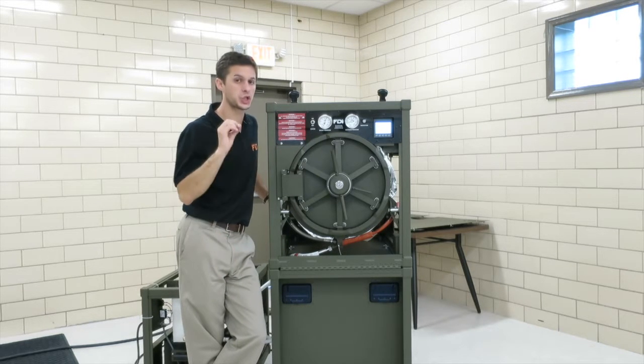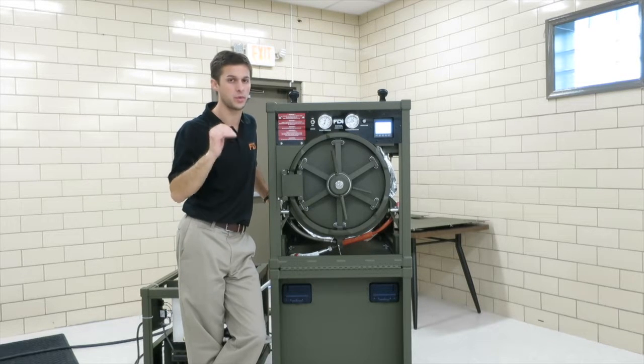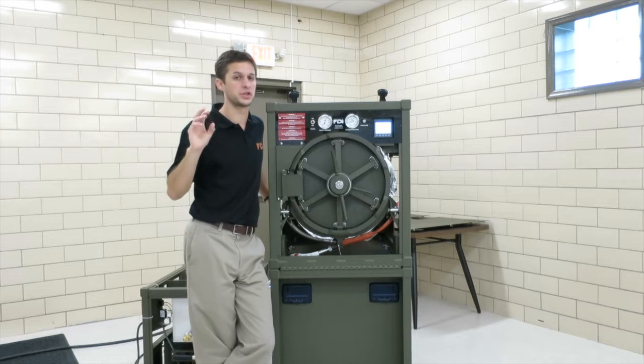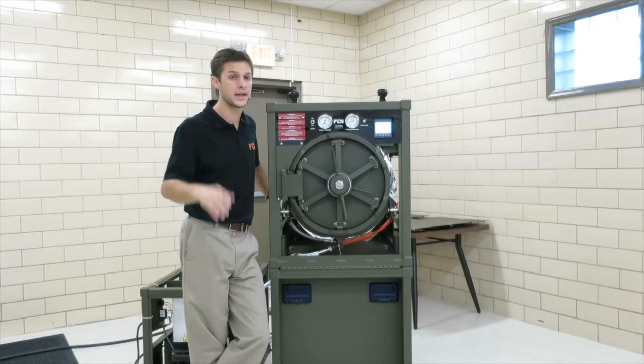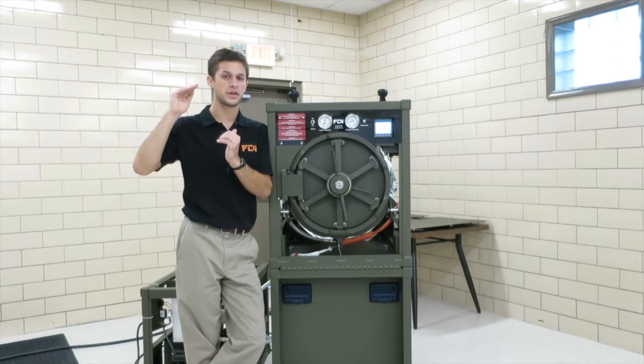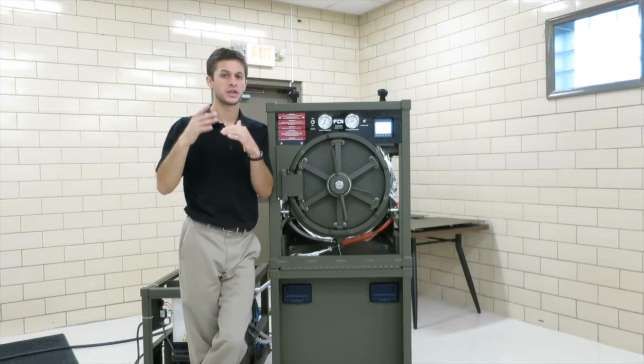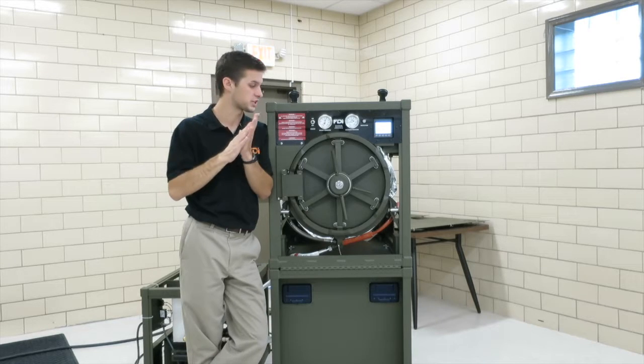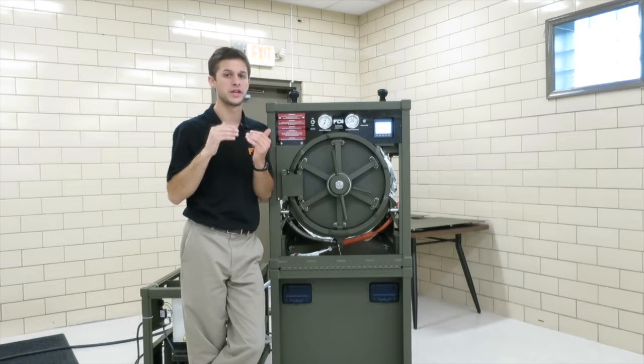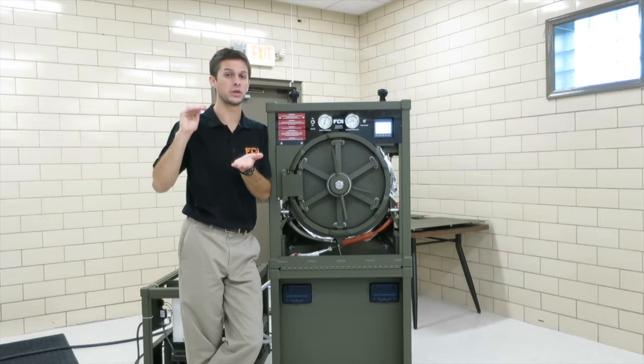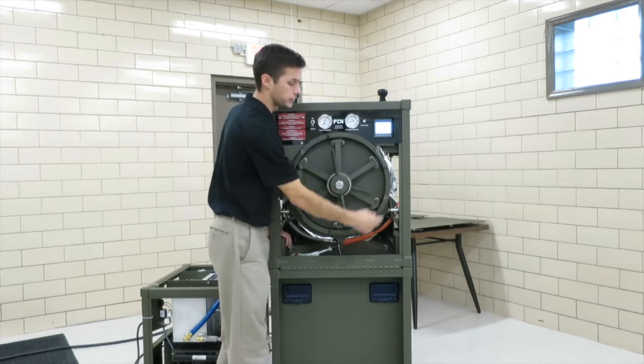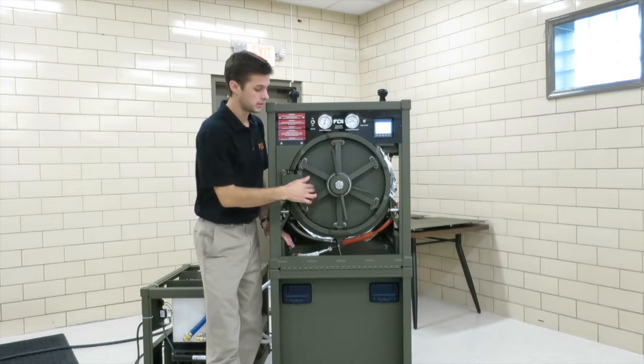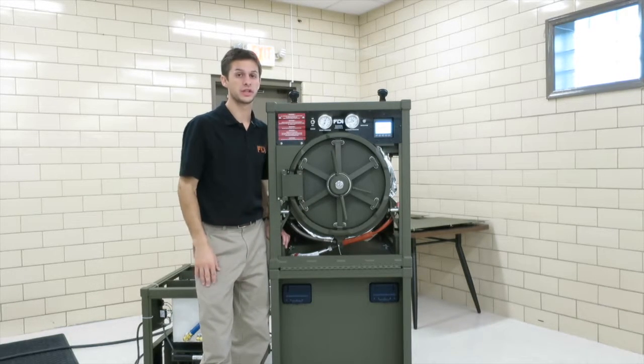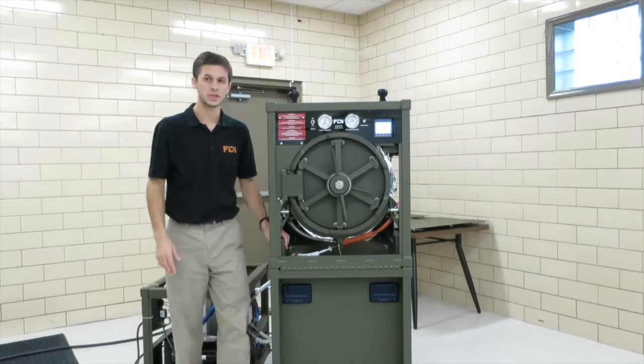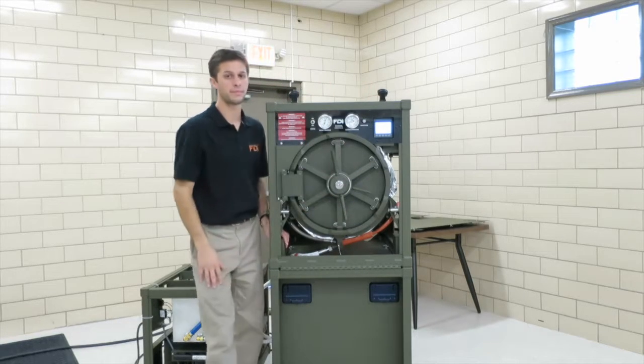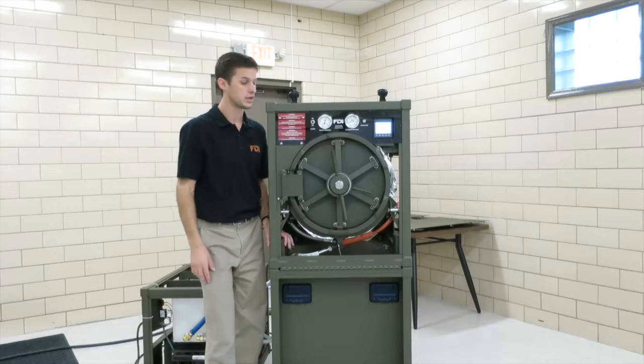So during exposure, to ensure that the chamber is indeed at 273 degrees, the set point, number 2 is also reading the temperature, saying, am I at 273 degrees? Am I low? Am I high? There's a little bit of a cushion. They can be off for a little bit, because of thermal expansion, contraction, there's a bunch of different things. They can be off by, say, a degree for a little amount of time, but if they're off for a minute or longer, you'll get this alarm, because the PLC will know element 2 is not agreeing with element 1. This chamber is really not at 273 degrees like we said it is, so you'll throw this alarm. So you're going to obviously want to check the probe, possibly transmitter problems in the electrical enclosure, possibly wiring problems too.